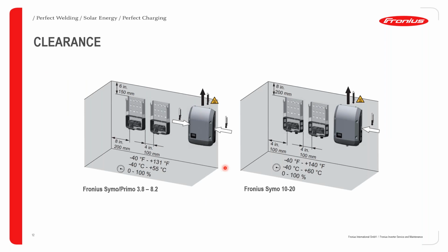Great, so now let's talk about clearance. For small Symos and Primos, a clearance of 150 millimeters is advised between the inverter and the ceiling upwards, and 200 millimeters from the inverter to the sidewall. If you're installing more than one inverter side by side, please ensure that the gap between the inverters is not less than 100 millimeters, as can be seen in the illustration. This enables the inverter to cool itself effectively, because we implement active cooling, where cool air comes into the inverter via the sides, and the hot air goes off from the top.